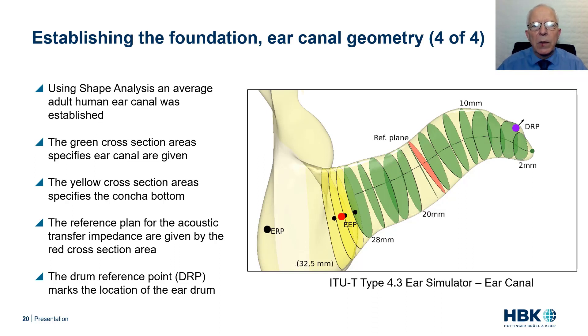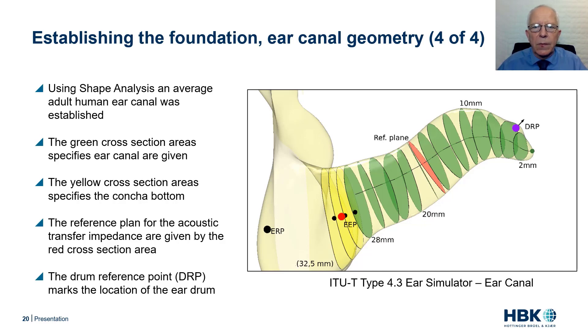The slide shows the average adult human ear canal geometry established using shape analysis. To have a description of the ear canal that can be easily documented — for instance in a standard — a few cross-section areas are used. Cross-section areas in green color relate to the ear canal geometry, whereas those in yellow relate to the concha. The EEP marks the ear entrance point; the DRP marks the drum reference point. The cross-section area in red is the reference plane, located approximately 19 millimeters from DRP, used as a reference plane for the acoustical impedance measurements.